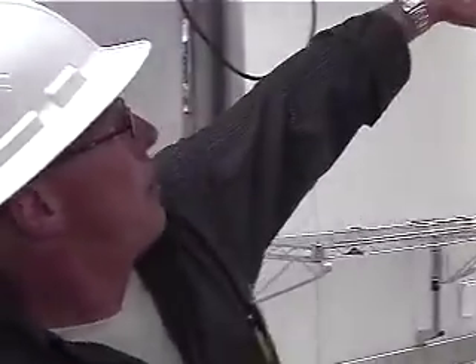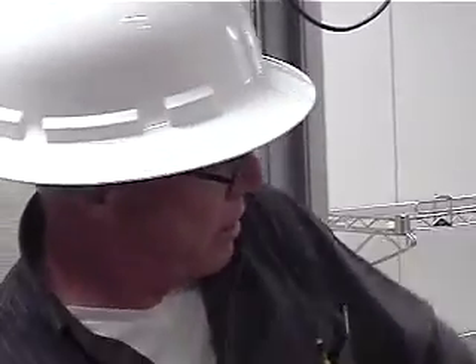If you're having a frosting problem, increase that. Just send that up to whatever it needs to be. It should only need one a day, unless it's one that has a whole lot of traffic. We've had them like this, we have a lot of traffic, and you don't have too many problems. Part of that reason is because of the way they're set up, you have an air screen that covers the door, so there's not a lot of moisture that's allowed to get into the room. Plus Utah's a pretty dry place.